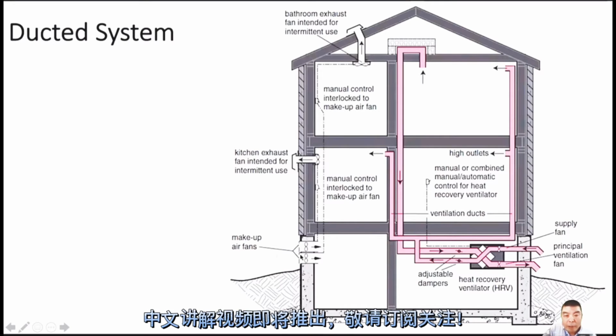So this is an exhaust fan, and this is a make-up air fan. Like we said before, we need air balance. If a kitchen exhaust hood has a big CFM, it draws lots of air outside, and the exhaust fan, even sometimes the dryer, draws air outside the building, and there's not enough air blowing inside the house. That's called unbalanced air pressure, which causes backdraft.